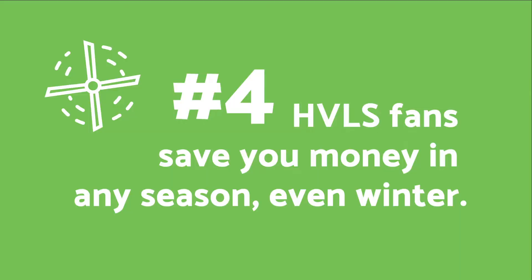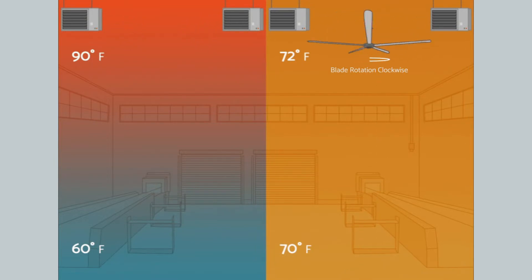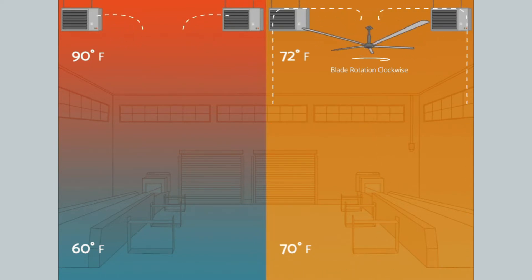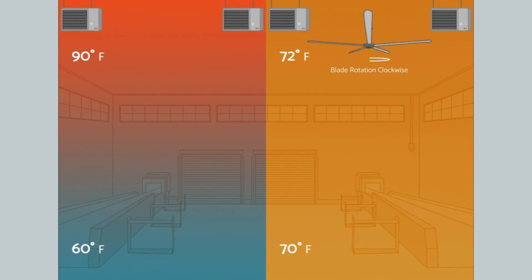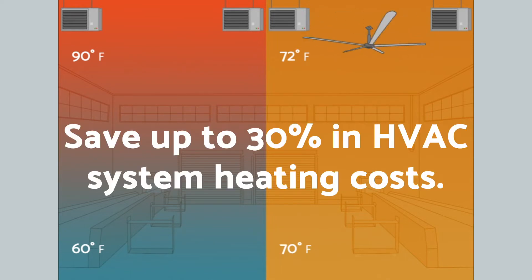Number four: HVLS fans save you money in any season, even winter. In the winter, through a process called destratification, HVLS fans run in reverse, sucking up the air and reducing the evaporative cooling effect that is produced when fans run counterclockwise. Hot air naturally rises and gets trapped at the ceiling, forcing cooler air to lay at the floor. With HVLS fans, the warm air is mixed with the cooler air at the floor to create an even temperature throughout the space. You can save up to 30% in HVAC system heating costs.